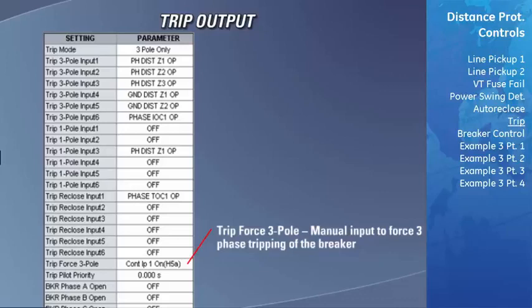The Trip Force 3-pole field allows you to input a command to the relay to force the D60 to immediately trip all 3 phases of the breaker. Often, this is an input that allows for manual input from a user, such as a contact input or a virtual input.